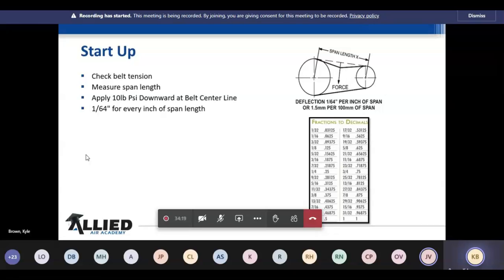What I'm trying to emphasize here is make sure you do whatever method you have. You'll see 10 pounds of pressure on the belt on the center line, 1/64th for every inch. I like to go by the 10 pounds PSI myself. That's me. And look at the deflection. The more you do this, the more you'll know exactly what is and isn't right. If you push on that belt and it doesn't move, you've got too much.